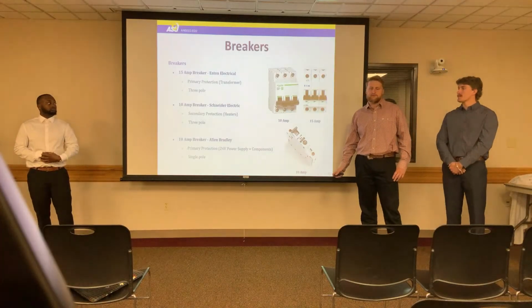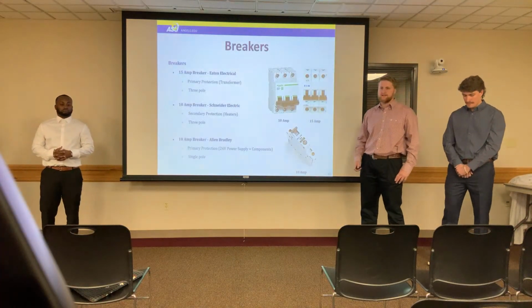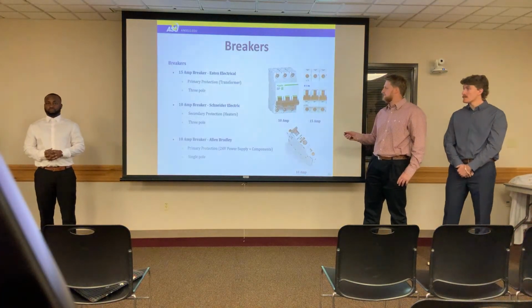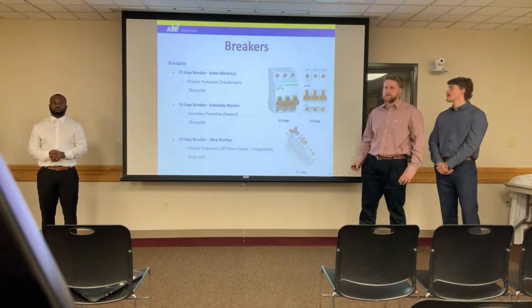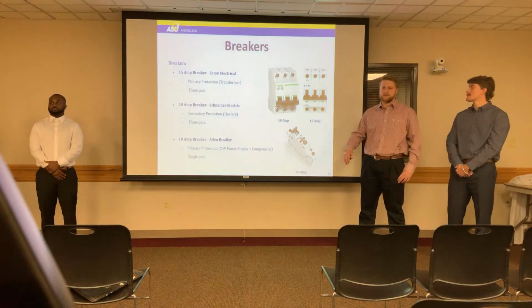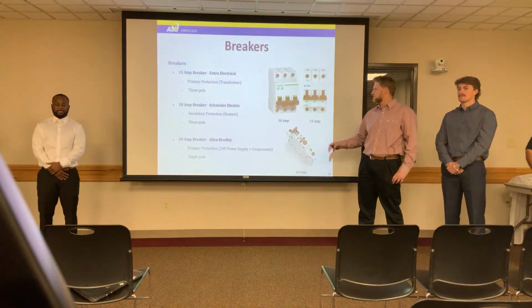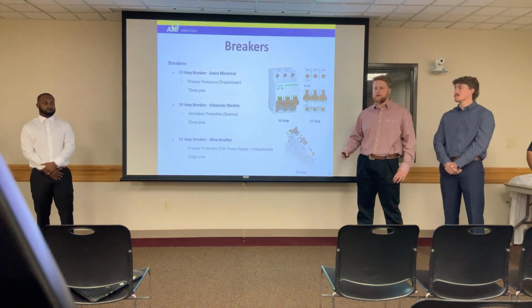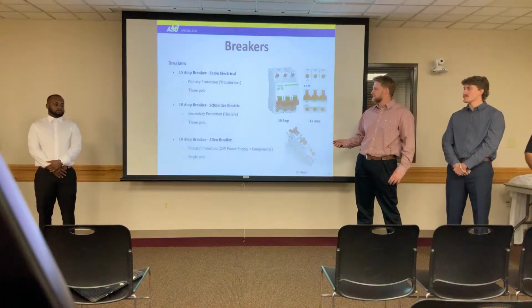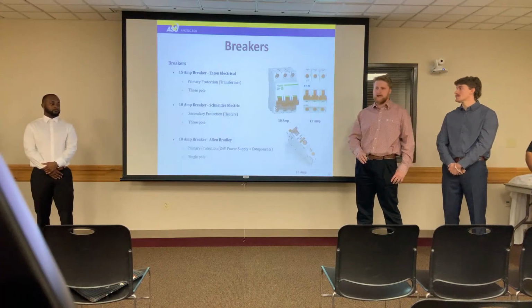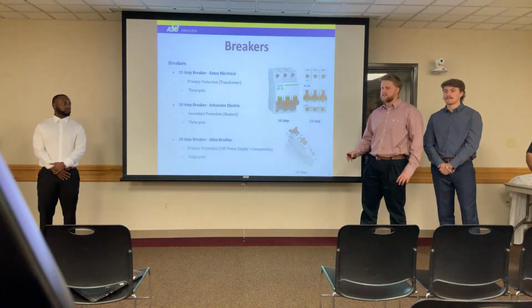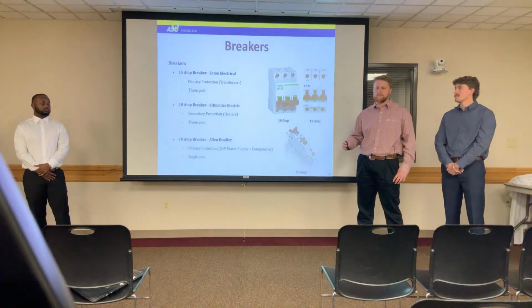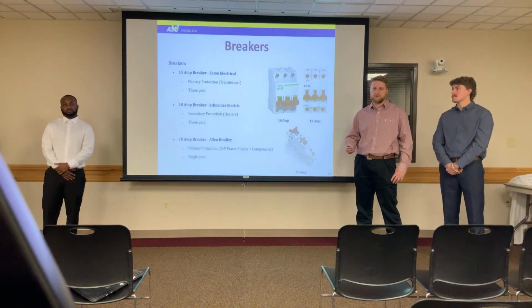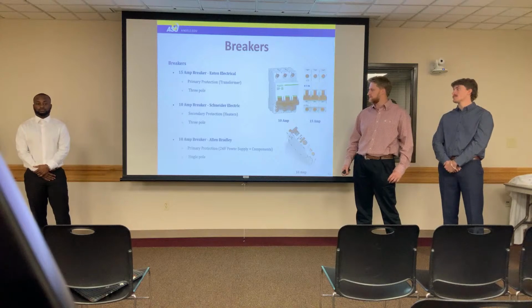We are using 3 breakers throughout the system in order to add some protection. The first one is a 15 amp breaker. This one is where the 480 volts will be directly plugged in. This will prevent overload of current flowing through the system. The next one is a 10 amp breaker. This will come after the transformer, and it protects the transformer itself from the power supply or heaters drawing too much current and damaging the transformer.